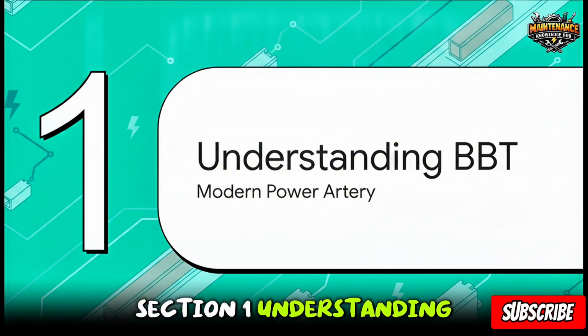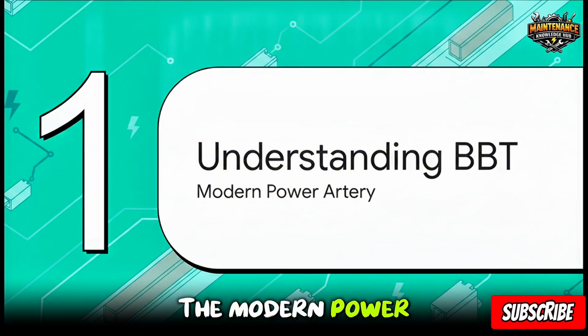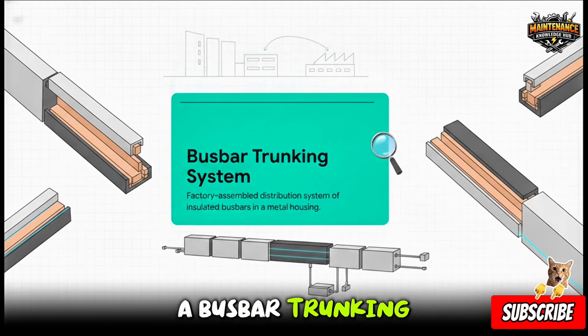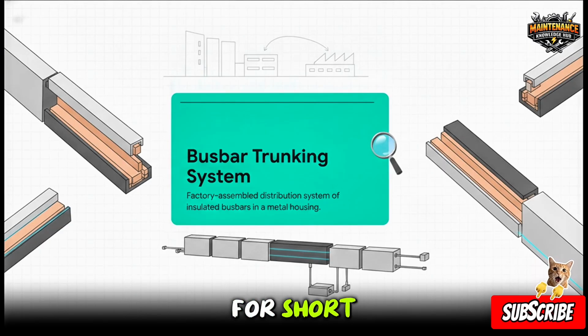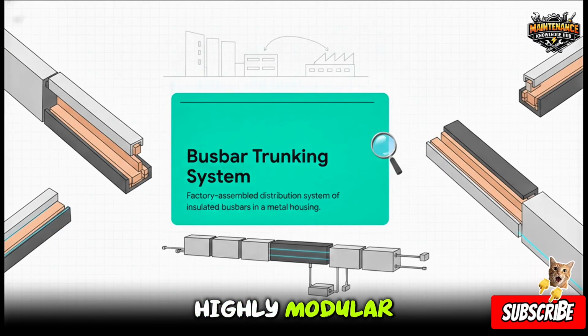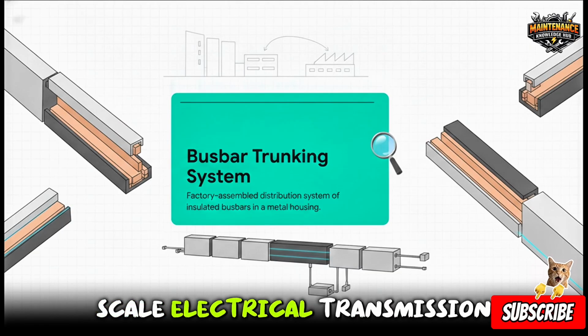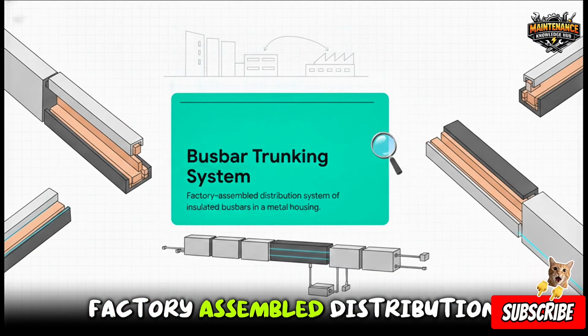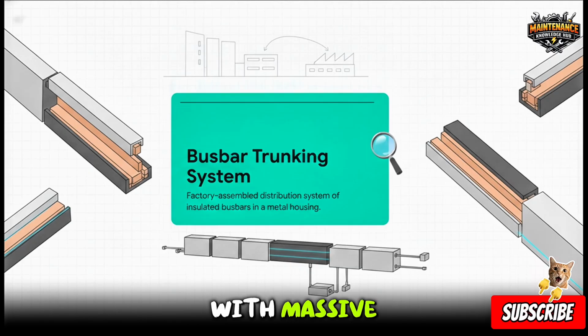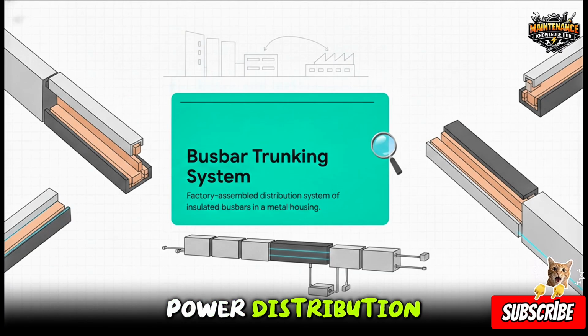Section 1. Understanding BBT, the modern power artery. So what is a busbar trunking system, or BBT for short? Essentially, it's the elegant, highly modular solution to large-scale electrical transmission. It's a completely factory-assembled distribution system. Instead of dealing with massive bundles of flexible wires, we're using rigid, heavily insulated copper or aluminum busbars, and they're all securely enclosed inside a protective metal housing. It literally replaces the need for huge, messy cable trays, bringing order, safety, and just immense capacity to power distribution.